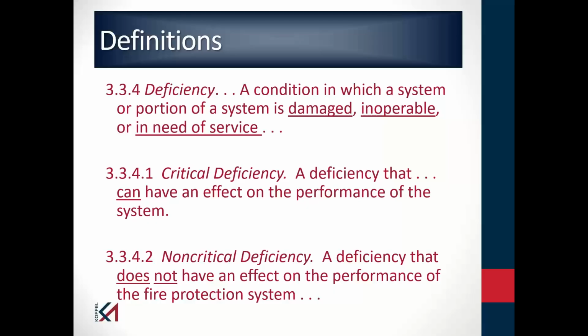NFPA 25, more recent editions, the ones we're talking about, 2015, 2017, do define something called a critical deficiency and a non-critical deficiency in addition to impairment. There's a table in the annex that helps me identify what is critical, what can have an adverse effect on the performance of the system, versus what is not critical.